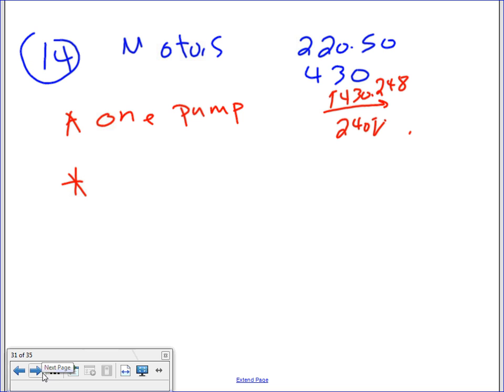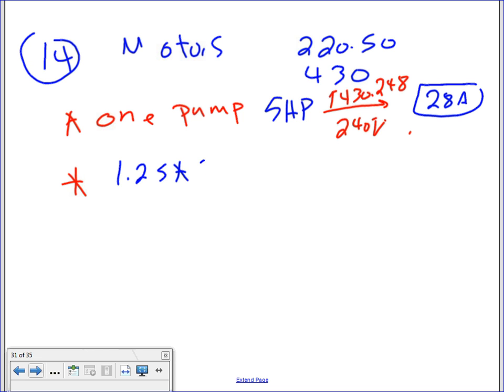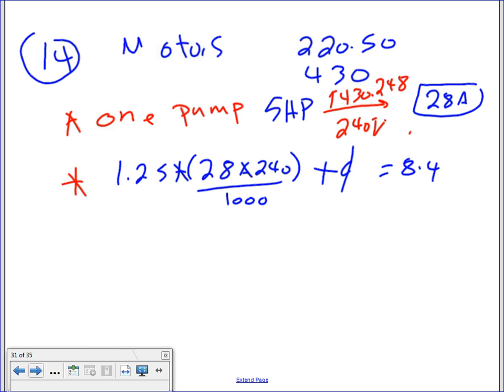Okay, motors. Now we're going to go to the step that talks about motors. We talked about fastened in place appliances. We're almost there. Motors. I only have one pump. It's a 5 horsepower pump. You're going to go to 430.248 on the 240, guys, or 230. You're going to find the 28 amps for it. You need to find the amps for the motor. 28 amps. Then, since it's the largest, we're assuming this is the largest motor in my system, so I'm going to take 1.25 times 28 times 240. Divide this by 1,000. Remember why? Because we're calculating everything in kVA. Plus all the other motors. There's 0 other motors. That will get you an 8.4 kVA.